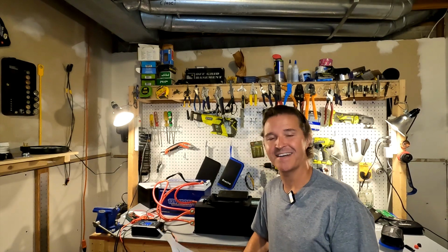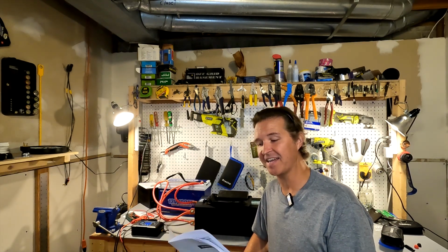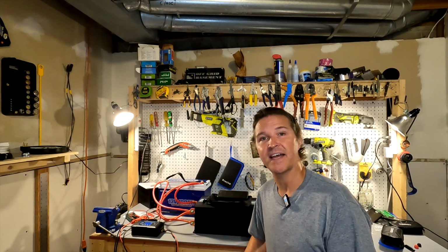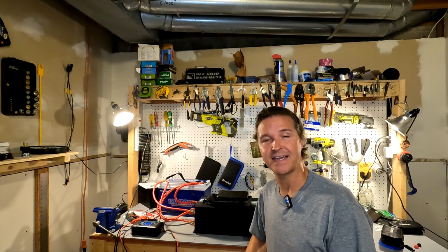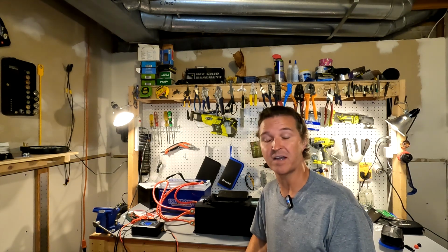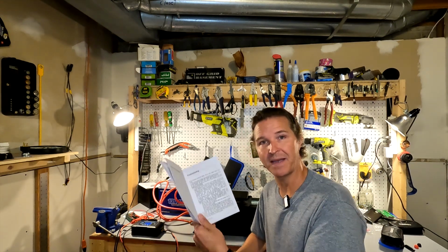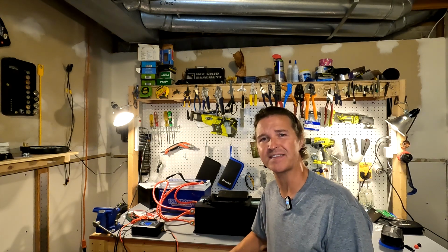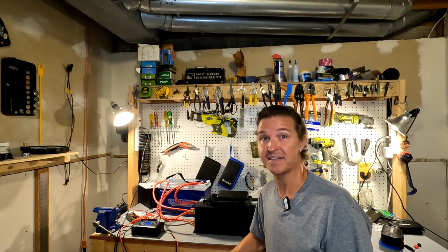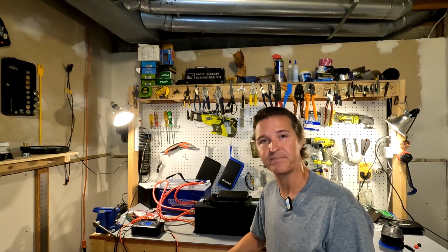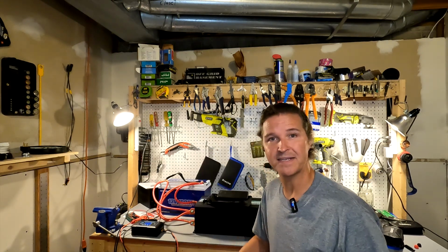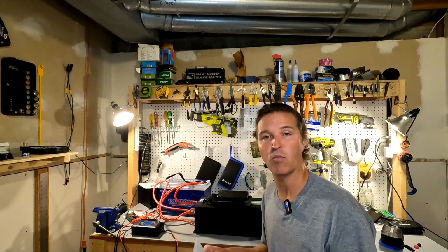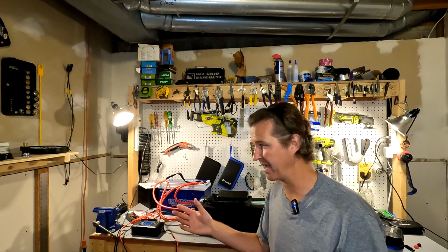I'm actually kind of disappointed with myself for not reading this in the troubleshooting of the manual. It does say that if your battery does turn off, you should keep it disconnected for 30 minutes and it will automatically recover. I'm just going to go with what the manual says to be true because I don't want to recreate this test, because I feel like it was stressed enough to pull 260 amps from this battery. So just remember, 30 minutes, try the battery again if you don't have a way of waking it up already by having a charger or another 12-volt source to wake up that BMS.